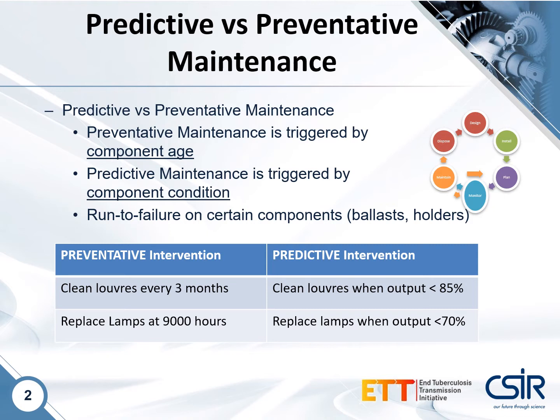manpower. However, these requirements don't necessarily hold true for UVGI installations in healthcare facilities, as UVGI installations will have significantly lower numbers of units within the facility, and the cost per unit is significantly higher than you would find for artificial ambient lighting. The predictive maintenance programs may therefore be more appropriate for ultraviolet systems. Your predictive maintenance activities, as opposed to the preventative maintenance activities, are triggered by component condition and not component age. And the component condition must be monitored and recorded.